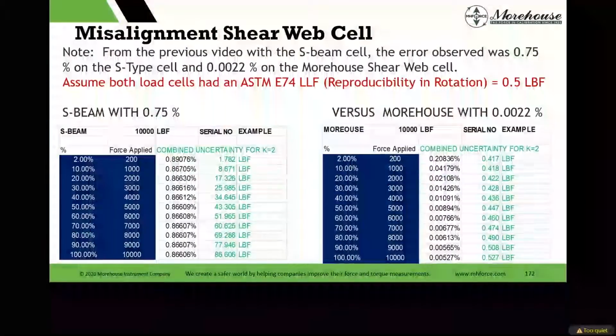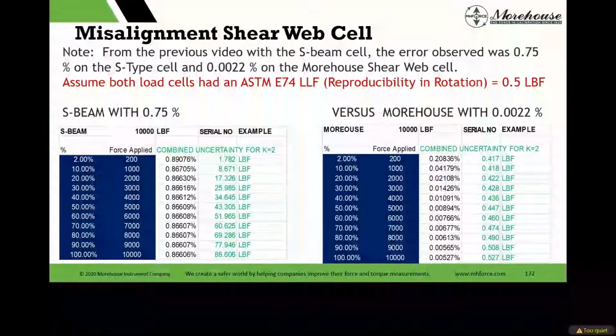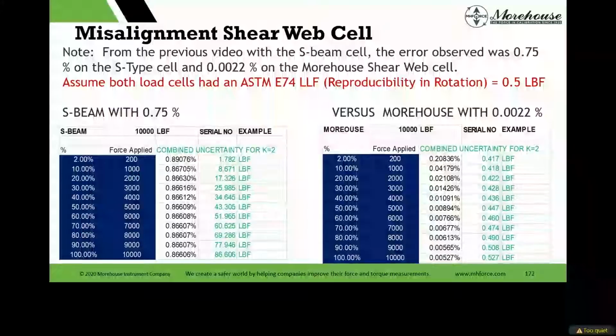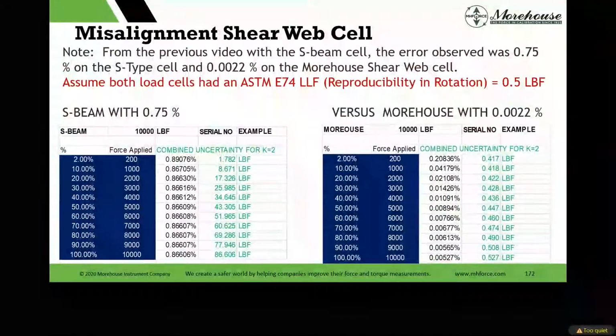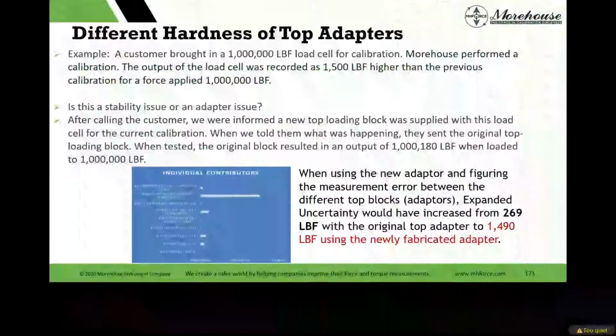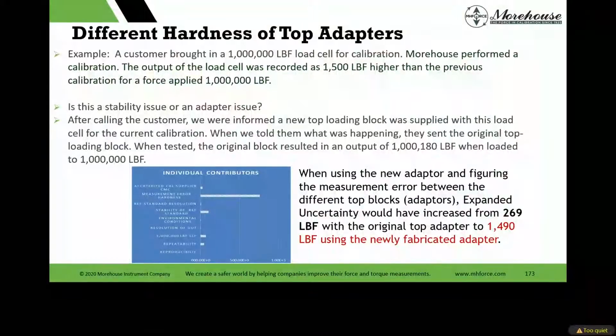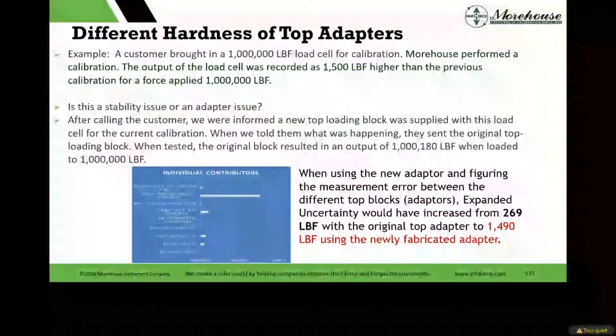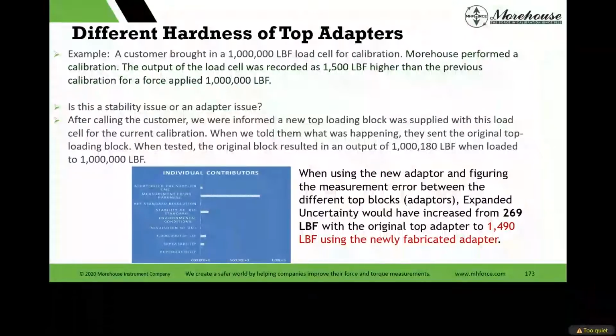Types of load cells. Again, that S-beam that was off center, that uncertainty really ballooned on us, whereas if we misaligned a shear web load cell, it wasn't nearly as bad. So there's a story on here, and I was the one doing the calibration. The customer had a 1,000,000-pound load cell, and I got numbers that were about 1,500 pounds higher than the previous calibration. So what our techs typically do, which is good practice, is once you get a cell in, you look at the old data. I mean, some people say don't look at the old data.